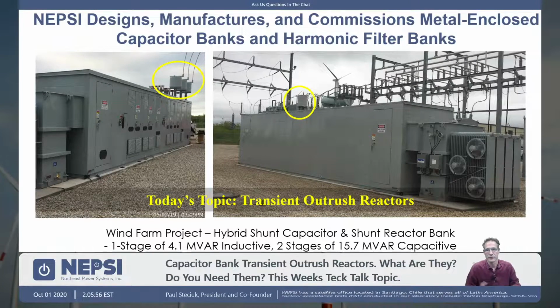And what we are showing you here is a piece of equipment that we designed, built, and shipped to a wind farm. In particular, I showed you a little yellow circle around what we are talking about today, which is outrush reactors. So this was a single stage 4.1 Mvar shunt inductive bank with a switch inside it to switch that inductor in and out, to basically compensate or apply negative VARs to the system, basically to reduce voltage. And it's also a two-stage cap bank. All switching, protection and control is built in, typical for metal-enclosed systems. So that is what we do, and we're talking about these devices up on top in the circle here.